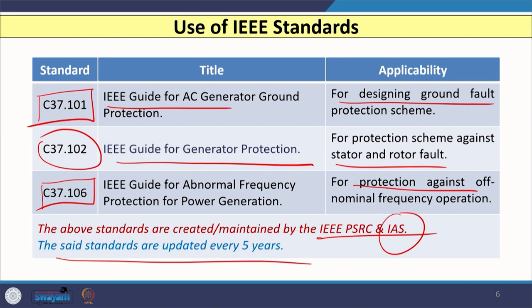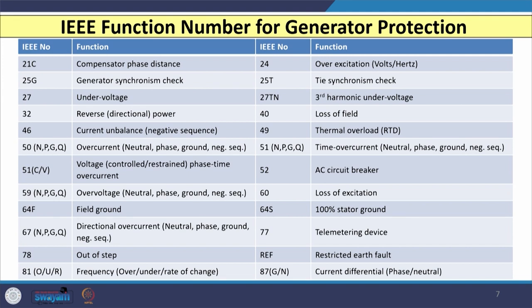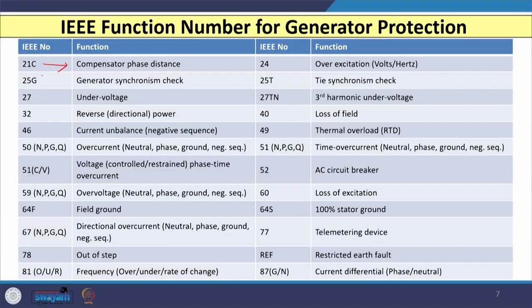Apart from those standards, there is an IEEE standard giving particular function numbers in generator protection. Function 21C is for compensator phase distance, normally used to achieve backup protection. 25G is for synchronism check. 27 is for under-voltage. 32 is for reversal of power — reverse power protection, which is directional in nature. 46 is for negative sequence. 50 is for over-current, which can be in the neutral circuit, phase circuit, ground circuit, or in the form of negative sequence.